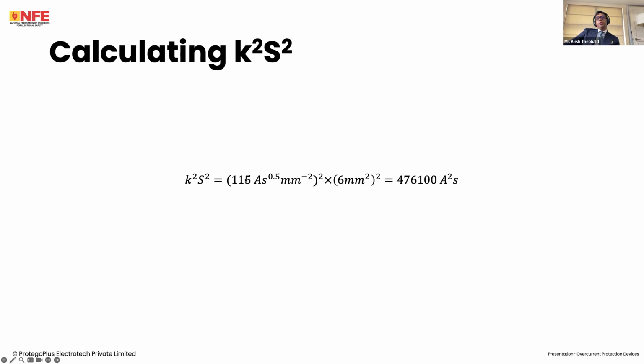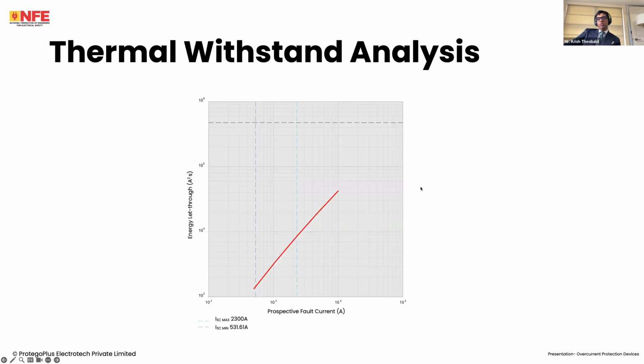So, what is K squared S squared? K squared S squared is 115 squared times 6 squared, which is 476,100 amp squared seconds. Now, let's plot this. This is our K squared S squared, which is also in amp squared seconds, 476,100. This is the value of prospective I squared T let through by the protective device. And this is the minimum short circuit current, 531.61 amps, and the maximum, 2300 amps. For all values between 2300 amps and 531 amps of short circuit current, K squared S squared is always greater than I squared T, because this graph is always lower than this point. Simple. And our withstand is taken care of.